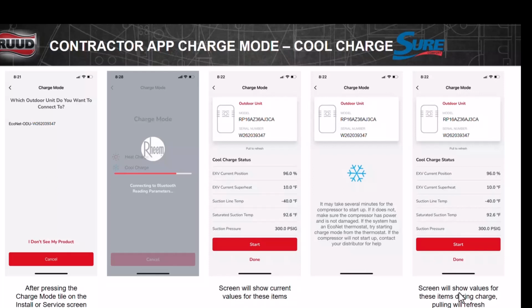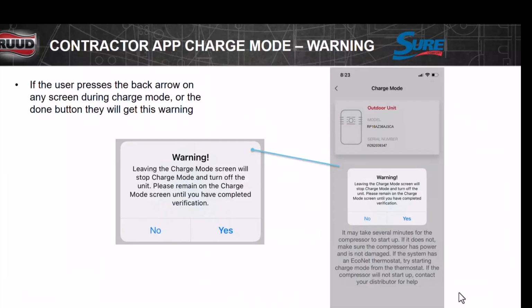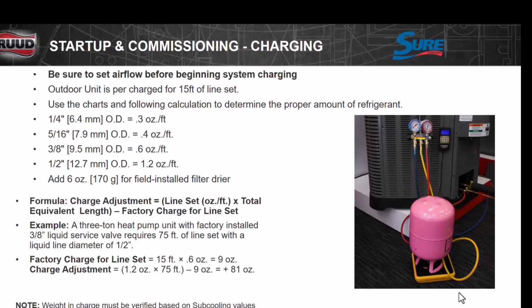So whenever you're doing this, you're going to be able to see what's going on outside. You'll see the suction line temperature, you'll see saturation temperature, and your suction pressure. Pressure transducers are sending that information to them. And there's also a cool charge mode along with the heat charge. So whenever you get it into charge mode, if you leave this screen, it will take it out of charge mode. So just be sure that you're keeping it on the charge screen whenever you leave, because if you take it out, it's going to throw this warning out. When you say yes, it's going to kick it out of charge mode. And you may not recognize that while you're sitting there charging it.